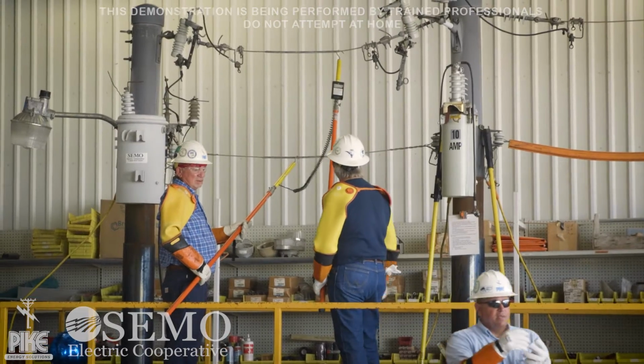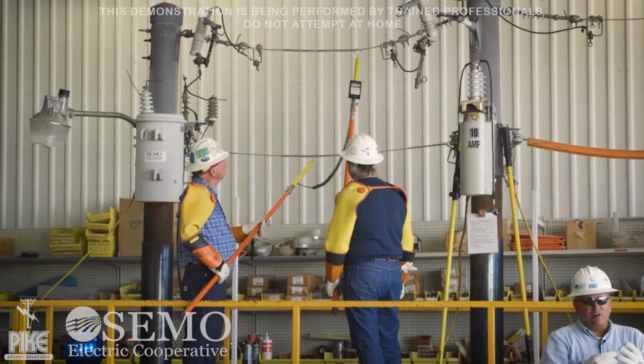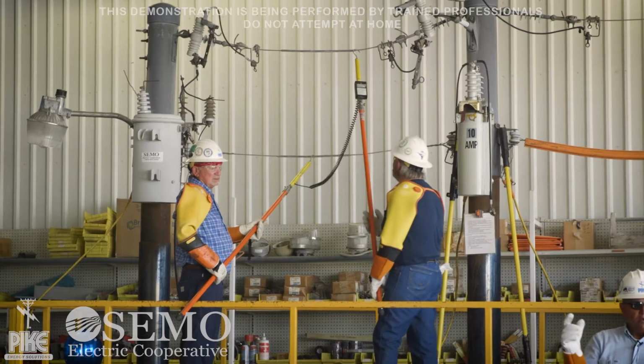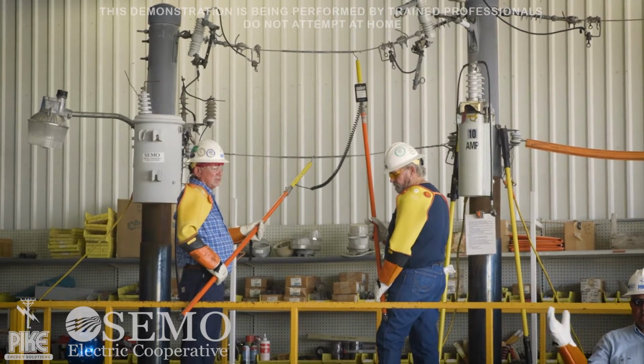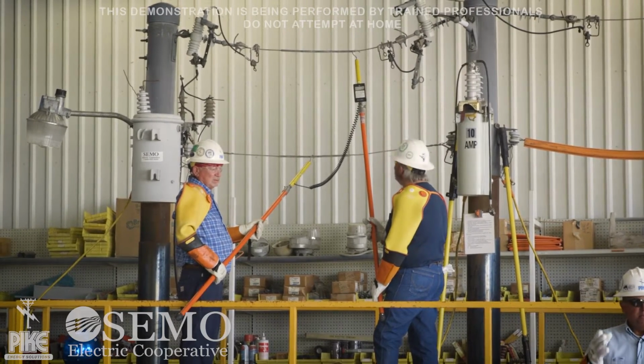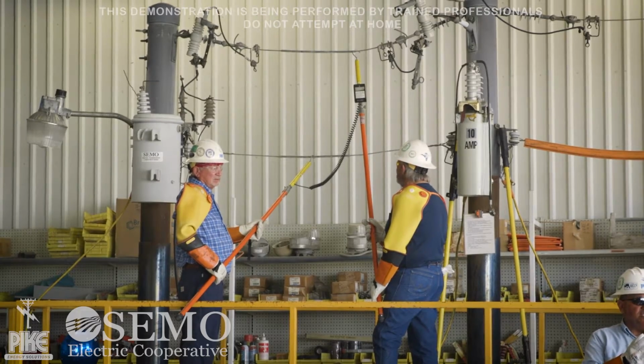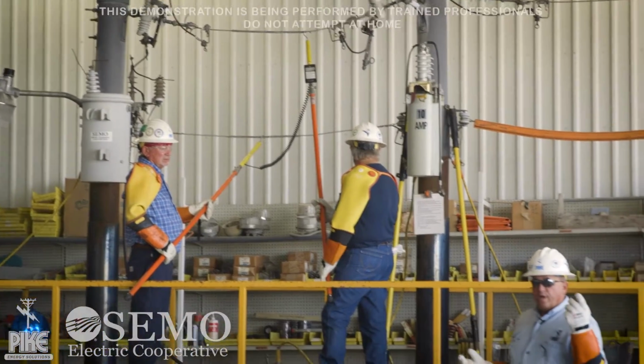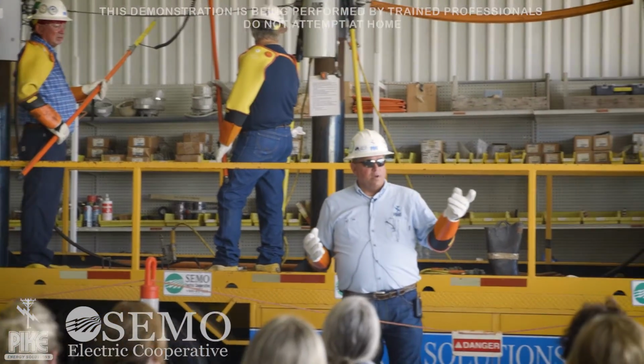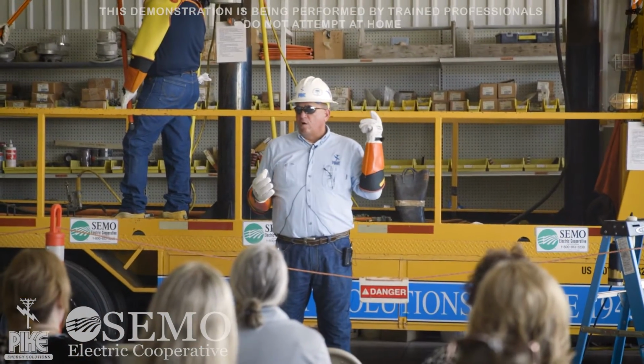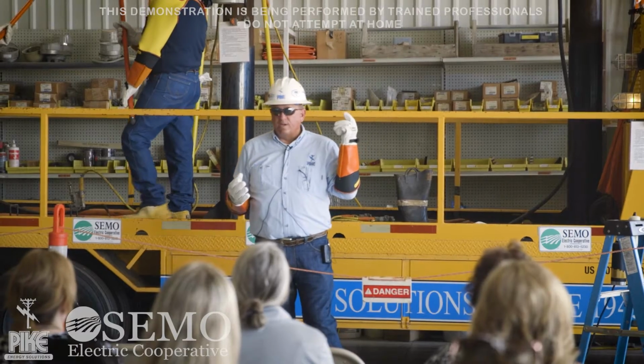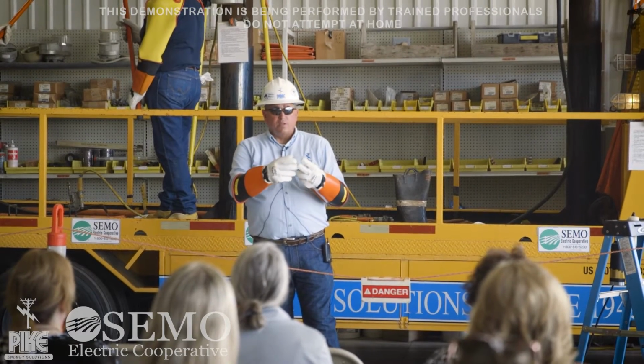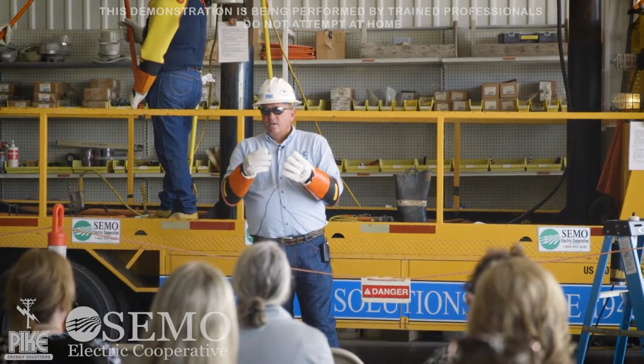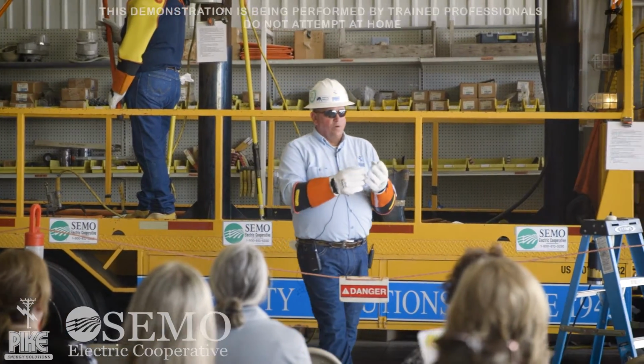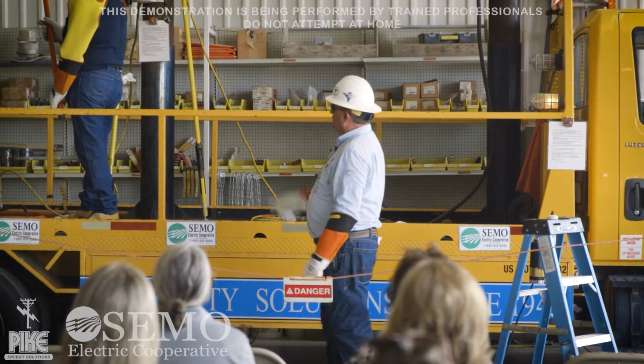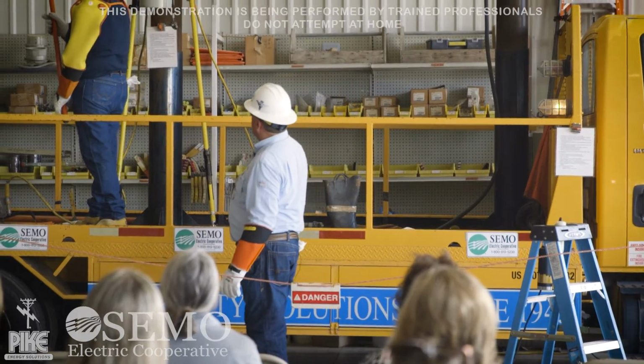So those 4 things, in that order, in my opinion, are very, very important. That visible opening, I got to make sure I have an air gap between the work location and the source, make sure I test the line, make sure there's no voltage. I could have backfeed from a generator. You know, Ron mentioned generators earlier. Basically here, just in a few moments, we're going to show you what backfeed is. We're going to demonstrate backfeed. So I want to make sure there's no backfeed. Number 3, I'm going to ground that line. Number 4, I'm going to flag and tag. Good. Go ahead and flag and tag it.